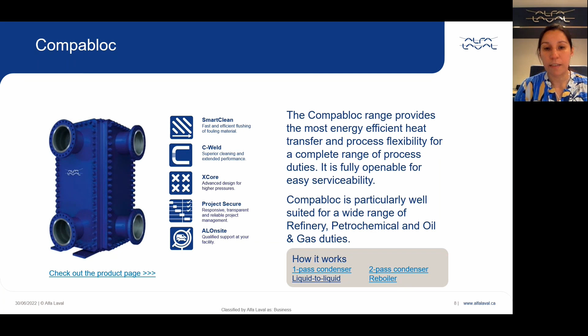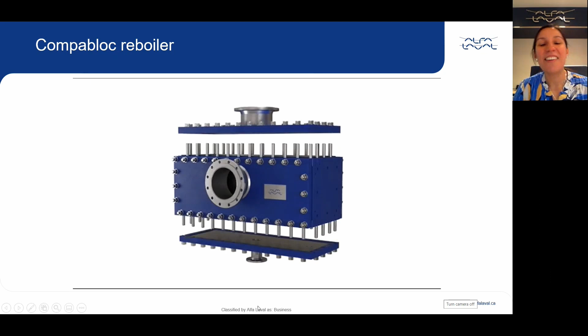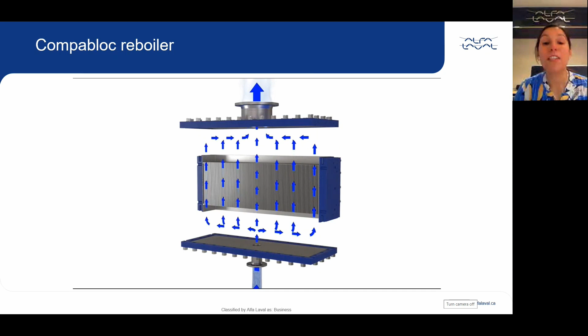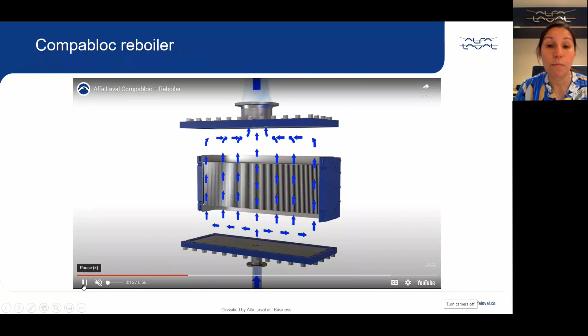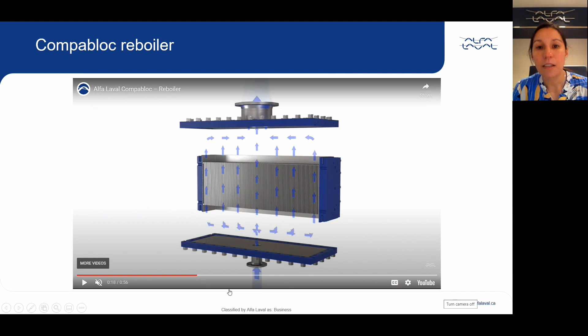Now, the Compabloc can also be used in two-phase applications or two-phase services, such as reboiling or condensing. And this is the reboiler configuration. Now you see it. For the reboiler, we have put the plate pack in a horizontal position. And now we have vertical channels for the reboiling fluid to pass through. So the Compabloc reboiler provides a very short length. So it's very efficient and it provides a very low pressure drop. So it's ideal for use as a reboiler.